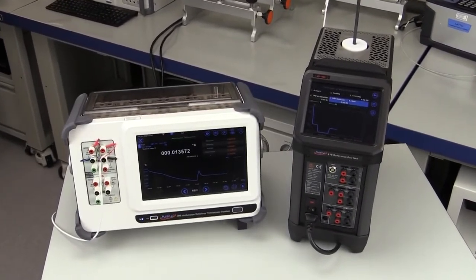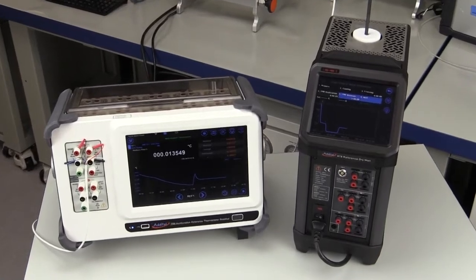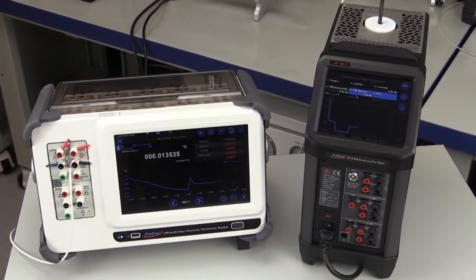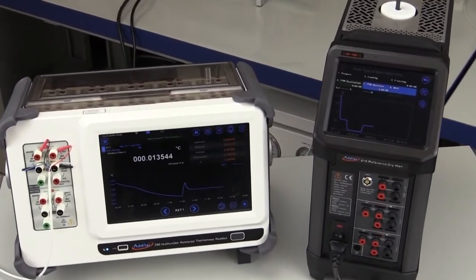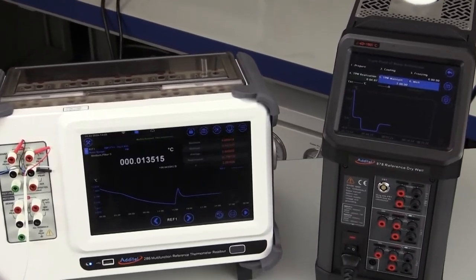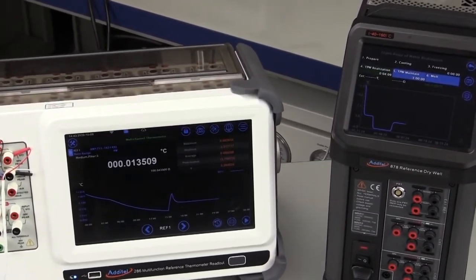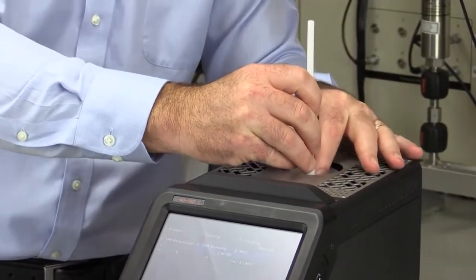With the ADT triple point of water system, you don't have to have the process option. An external readout can be used and the program will run the same with the exception of the automated update of the resistance of the triple point of water. The cell plateau will last long enough for you to perform a measurement on up to 4 non-pre-cooled reference thermometers.